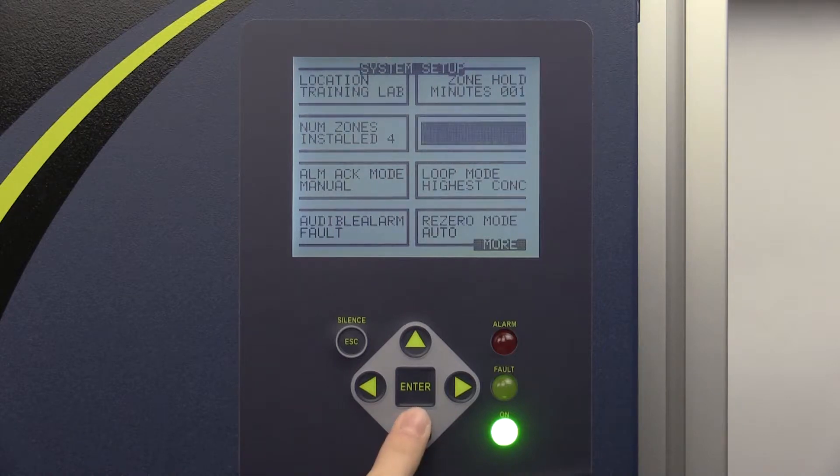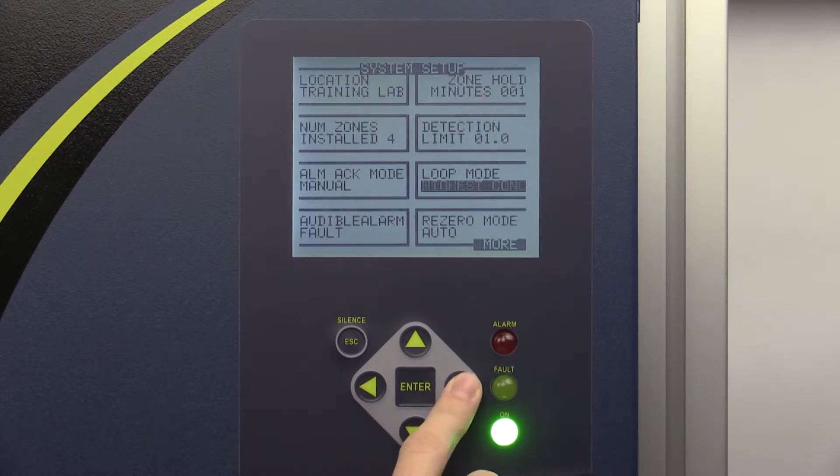Loop mode allows you to set the loop mode of two optional 4 to 20 milliamp outputs. In track zone mode, the device adjusts the zone and PPM outputs to correspond to the latest sampled zone number and its correspondent PPM reading, respectively.